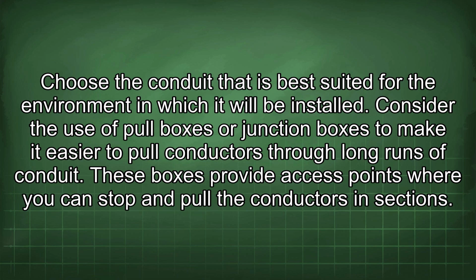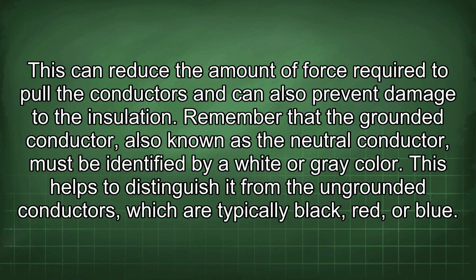Consider the use of pull boxes or junction boxes to make it easier to pull conductors through long runs of conduit. These boxes provide access points where you can stop and pull the conductors in sections. This can reduce the amount of force required to pull the conductors and can also prevent damage to the insulation.